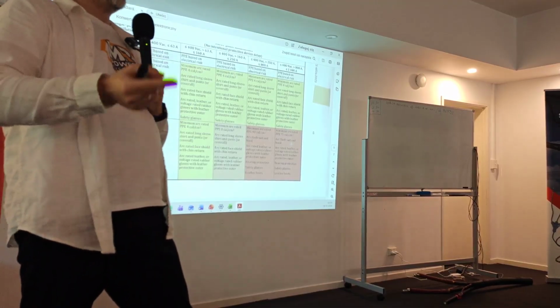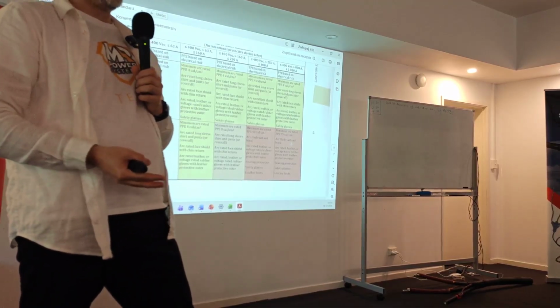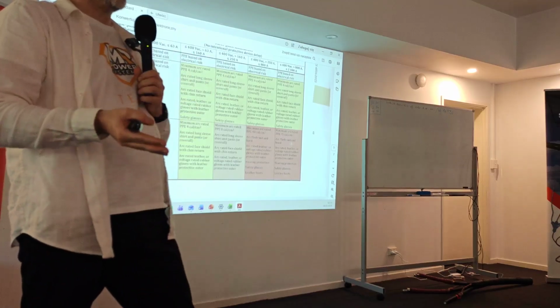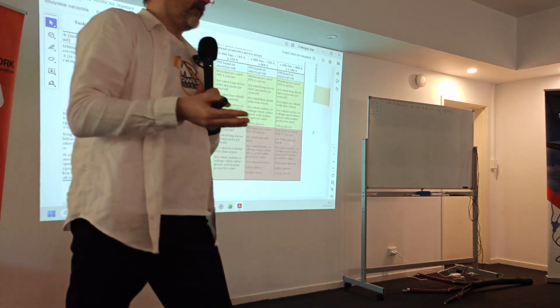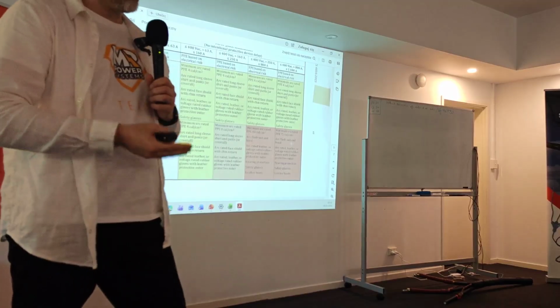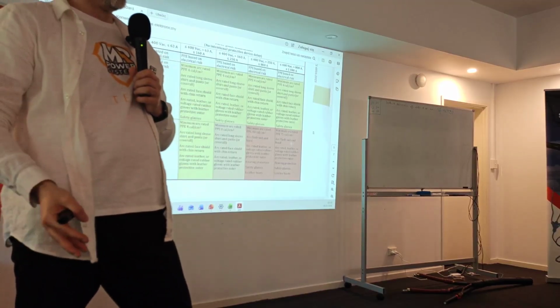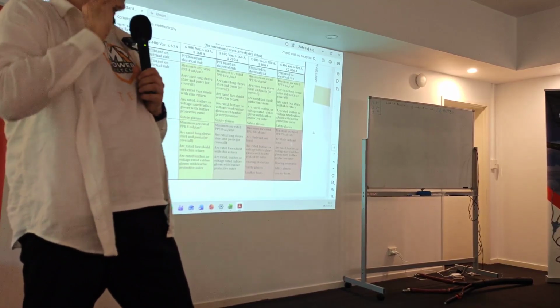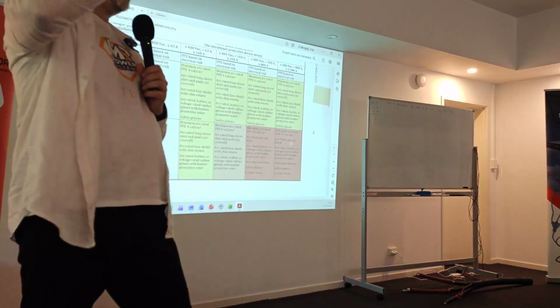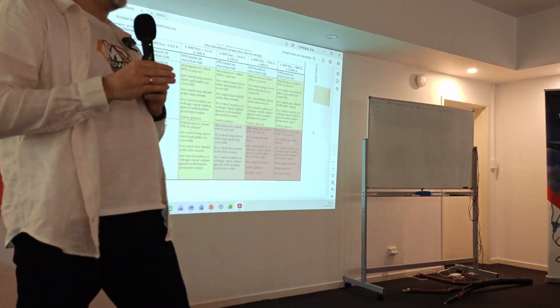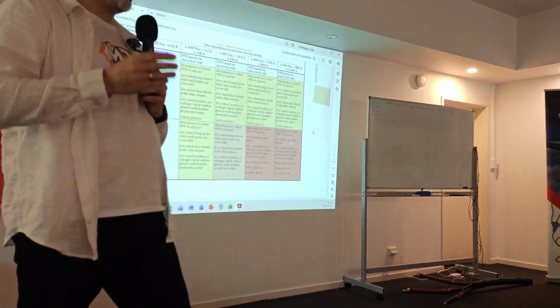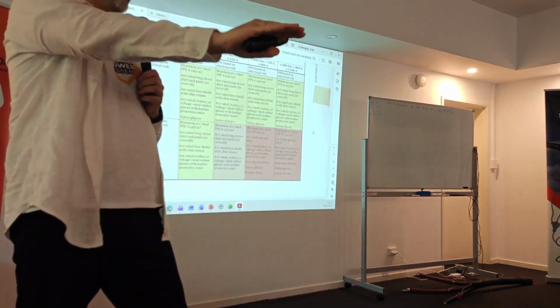So you can use some software. Not every software has it, technically speaking. Or you can use the Lee method, which is a base calculation for arc flash, but it's very conservative and will give you very high results at the end. So it's not what we want. The goal is not to be as low as possible, it's to be as close as possible to reality.